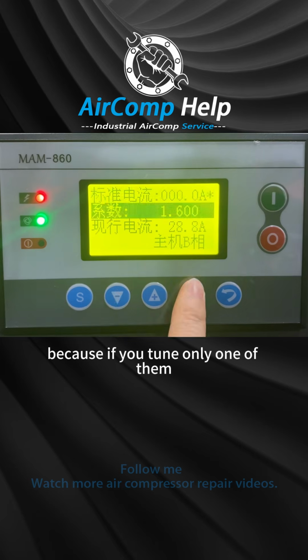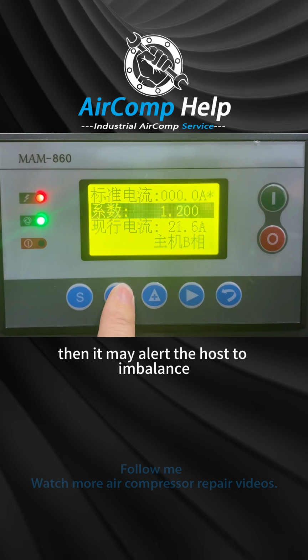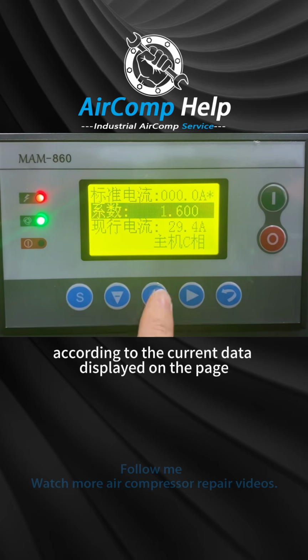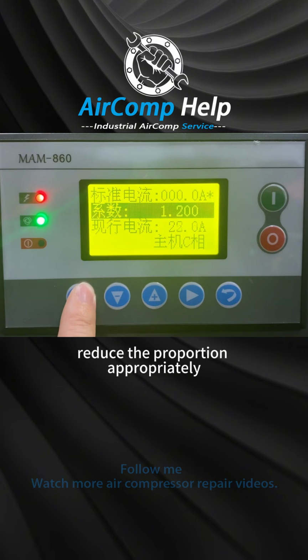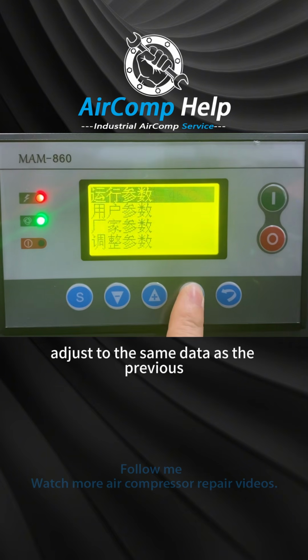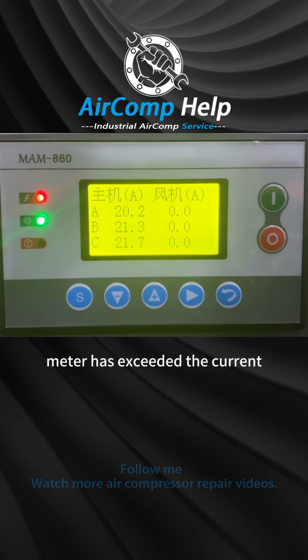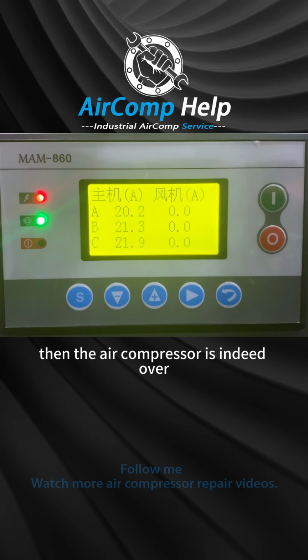Because if you tune only one of them, then it may alert the host to imbalance, according to the current data displayed on the page. Reduce the proportion appropriately, and adjust to the same data as the clamp meter. If the measured data of the clamp meter has exceeded the current, then the air compressor is indeed overloaded.